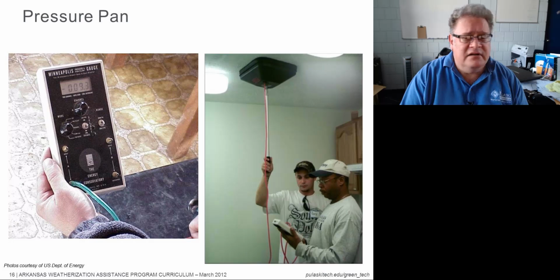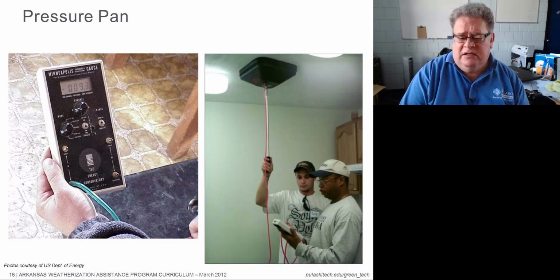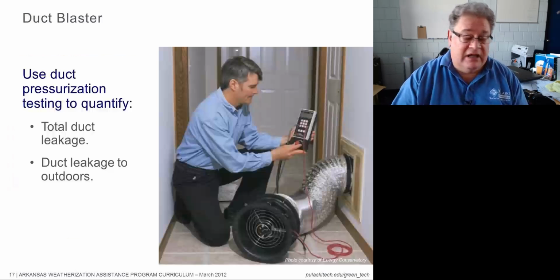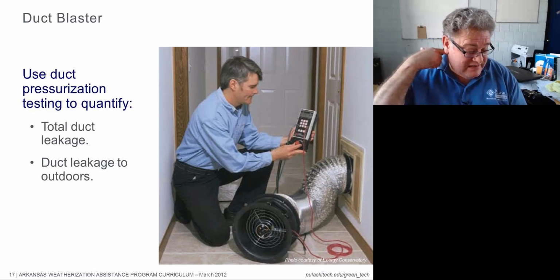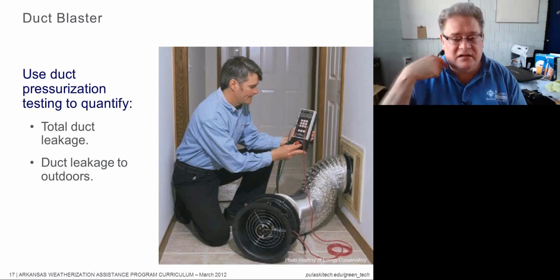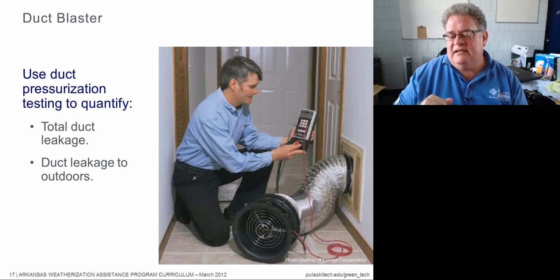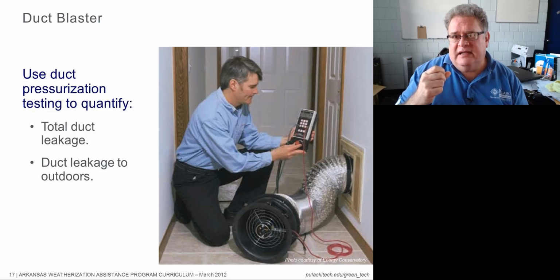Let's look at the next one here. All right, duct blowers. Duct blowers test duct leakage a lot more accurately than pressure pans. As a matter of fact, pressure pans don't test duct leakage. What they're actually testing is for a path. They're testing air barriers, and if the duct has one good air barrier, which it should, then it will test at 0. There will be no difference between what's in the duct and what's outside the duct, which is what we're comparing.